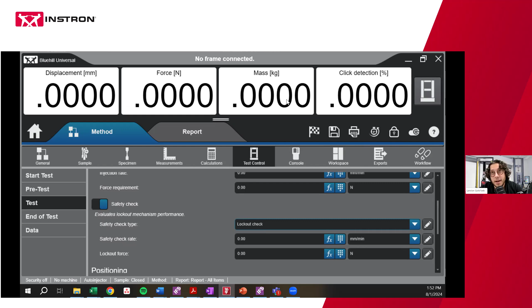So I have another question. Without a full enclosure around the system, how does the microphone handle ambient noise? Yeah, so I didn't bring attention to this, but you can actually see it behind me. The system has a light curtain as the front enclosure as opposed to a physical door. A big part of the justification for that was we have a lot of customers who are testing hundreds of these devices in a single sample. And from an ergonomic perspective, they really didn't want to be opening and closing a door for every test, twice a test. So having the light curtain was a much more user friendly solution.